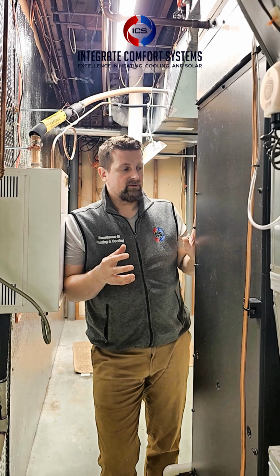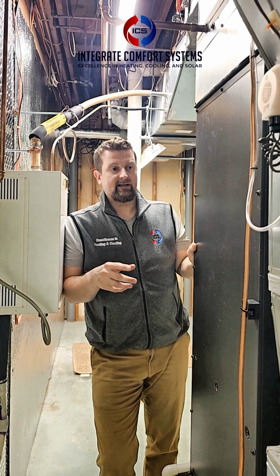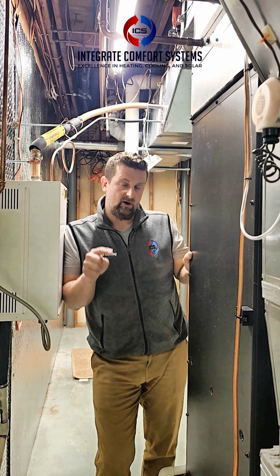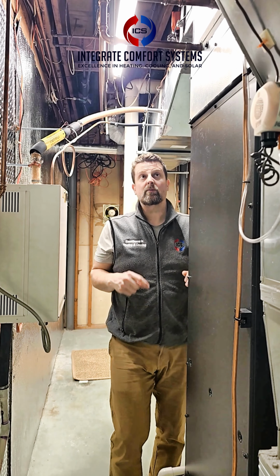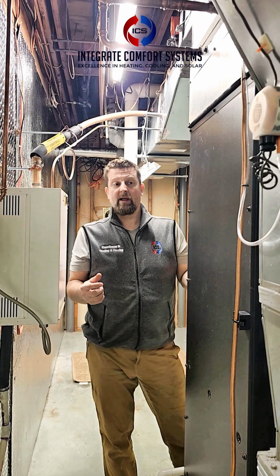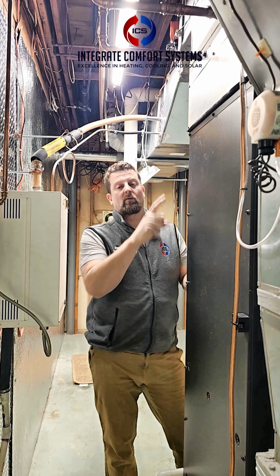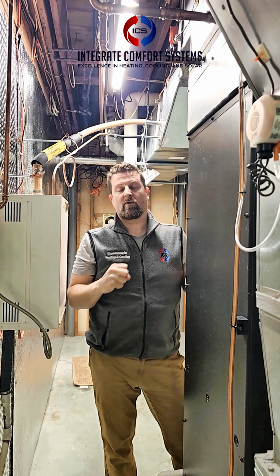While the air conditioning system runs on the cooler or milder days, we don't have much cooling load. Typically the AC system would run and run, and of course stop once it makes temperature, but it may not run long enough to properly remove humidity from your home. So what we're doing is, while we're cooling, we're also adding a little heating from the hot water coil, so as not to overcool the space.